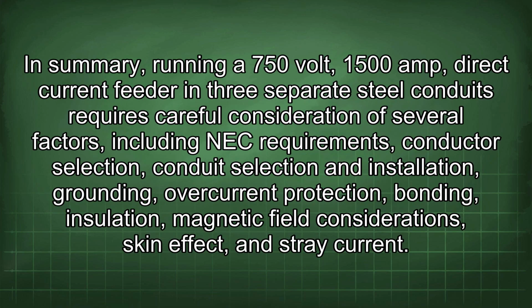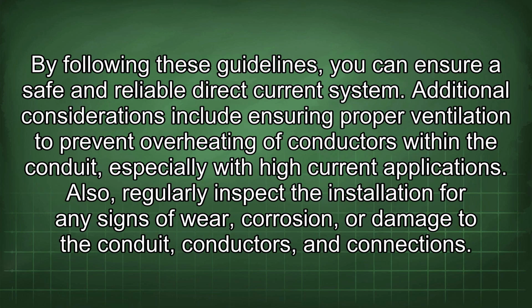In summary, running a 750 volt, 1500 amp direct current feeder in 3 separate steel conduits requires careful consideration of several factors, including NEC requirements, conductor selection, conduit selection and installation, grounding, overcurrent protection, bonding, insulation, magnetic field considerations, skin effect, and stray current. By following these guidelines, you can ensure a safe and reliable direct current system.